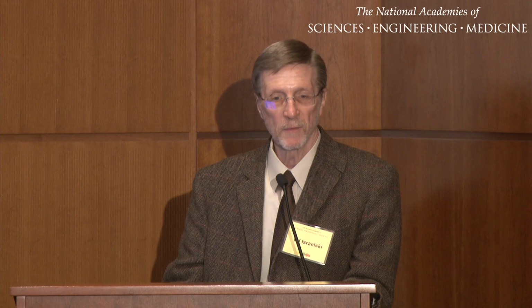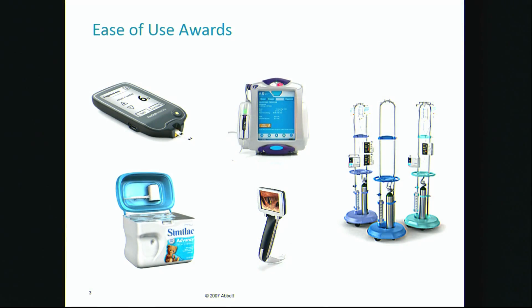A lot of good products in the medical field have employed human factors. The FDA requires it. To get a CE mark in the European Union, you must follow the international standards on human factors. I have a slide at the end which lists some of these for your reference. This is now a regulatory requirement.